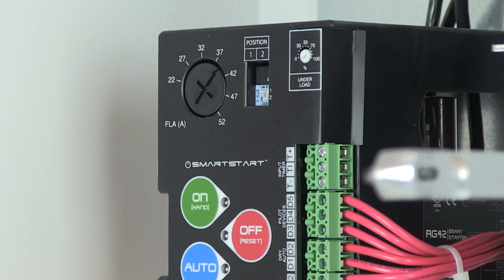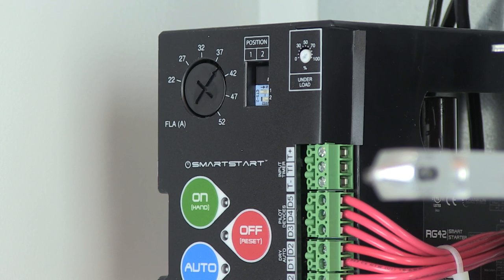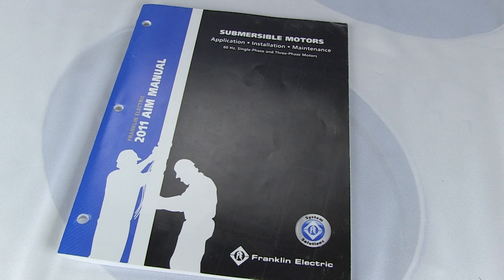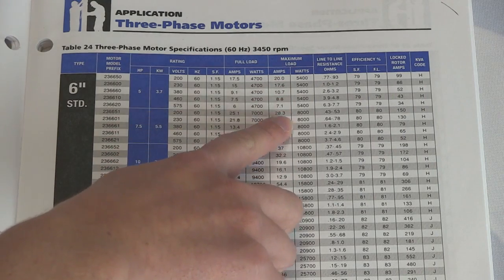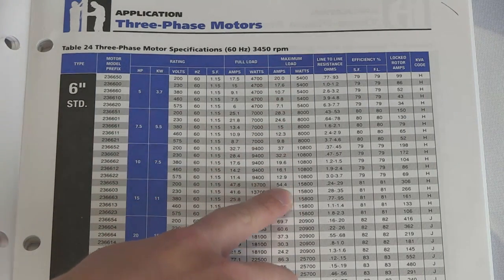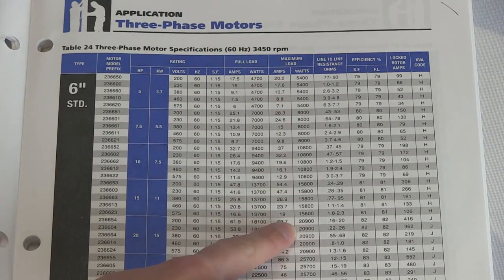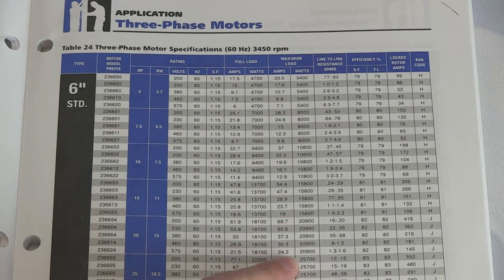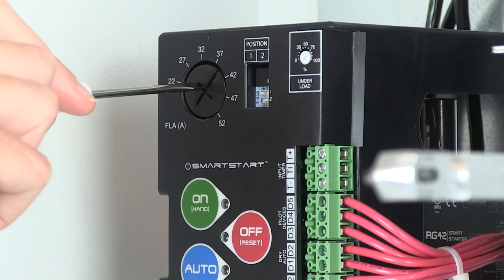Now, let's go over how to properly set your overload. To set the overload protection correctly, we need to set the overload dial to the max running amps of the motor. To find the max amps of your motor, please reference the service factor amps, or SFA, on either the motor nameplate or the Franklin AIM manual. For example, if the SFA is 24 amps, we would set the dial to 24.